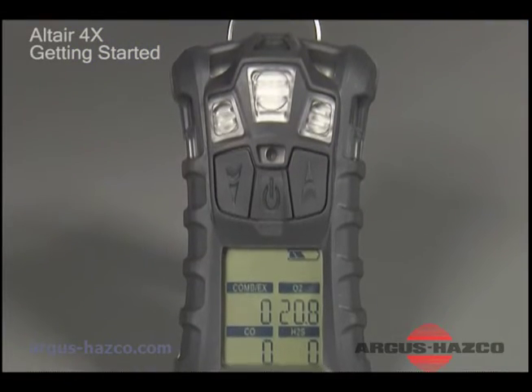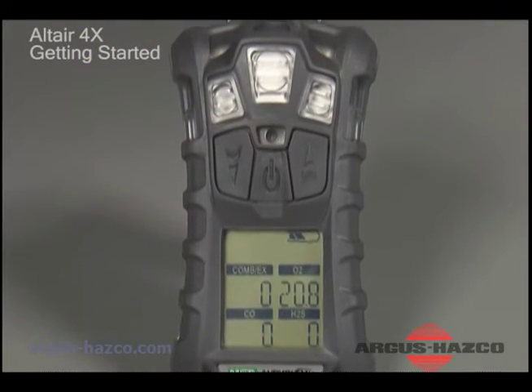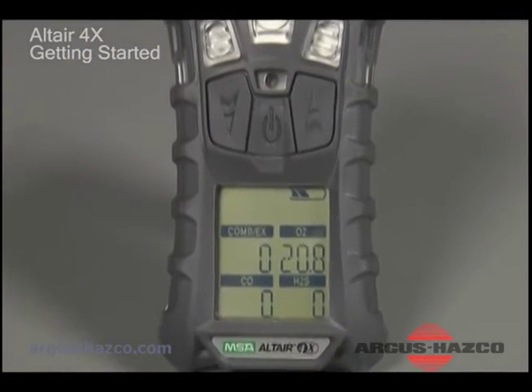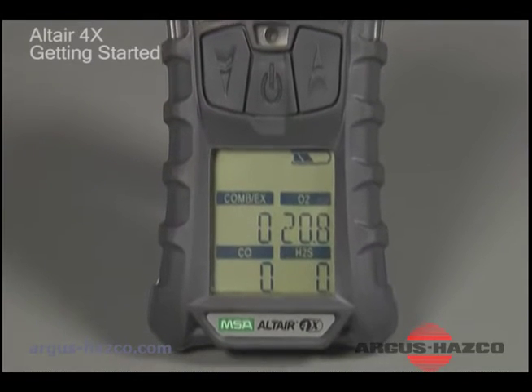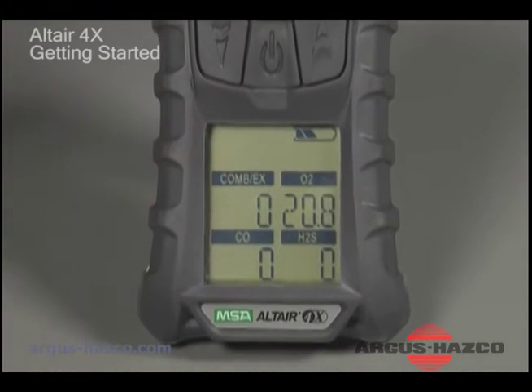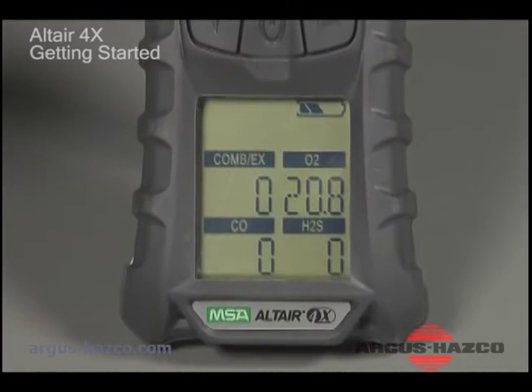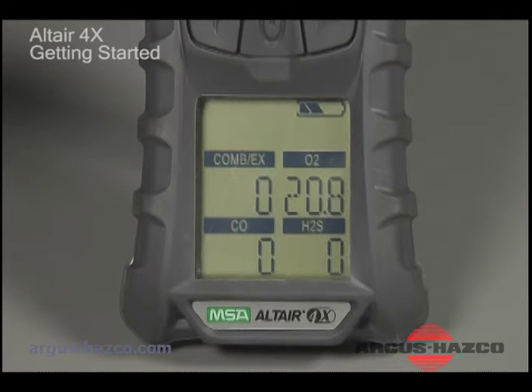Following the startup sequence, the detector will enter measure or standard operating mode. Increasing and decreasing gas concentrations are indicated on the display under each gas type. Remaining battery charge is also indicated in measure mode.